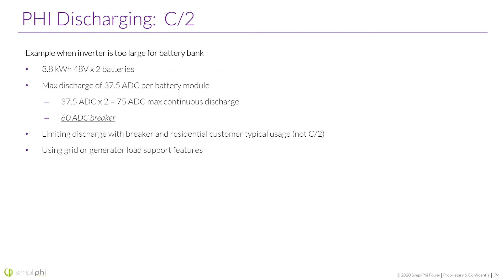There are some other functions in inverters that can help with over discharge, like grid support or generator. Actually, sorry, grid support's a bit of a different function, but load support, I should say, or generator support, is basically saying, hey, I can only discharge this much out of the batteries, turn on the grid or the generator when the load exceeds that amount. Now, this relies on the generator being gassed up or the grid being present. So again, not surefire. If you just follow our sizing guides, you should never have an over discharge event. So it's as easy as that.